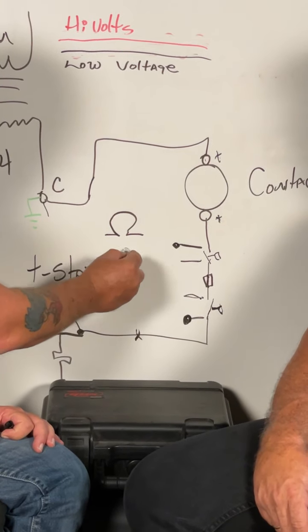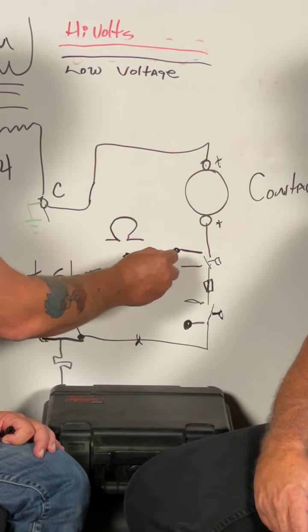We were talking earlier about this connection down here. If this is all good, and I have 24 volts, and I don't get my 24 volts here, and you check your low pressure, and you check your high pressure, and you find out, because the guys will check those on continuity to where you hear the tone, that only means that there is some resistance here. It doesn't tell you what the resistance is. So I have guys go from this point to this point, and I want you to use ohms, not continuity. And if you have 50 ohms between here and here, that's no good. This should be more like 0.5 or 0.05 resistance.